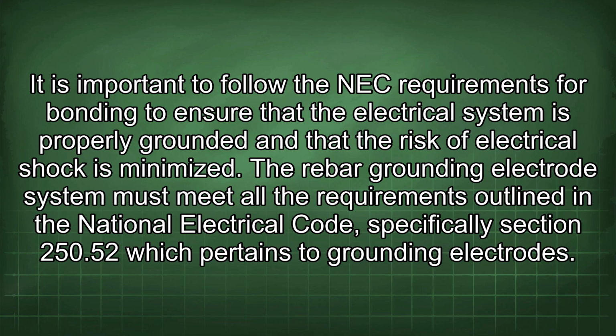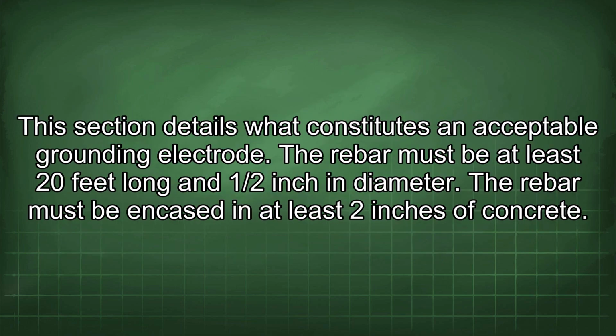The rebar grounding electrode system must meet all the requirements outlined in the National Electrical Code, specifically Section 250.52, which pertains to grounding electrodes. This section details what constitutes an acceptable grounding electrode. The rebar must be at least 20 feet long and 1/2 inch in diameter.